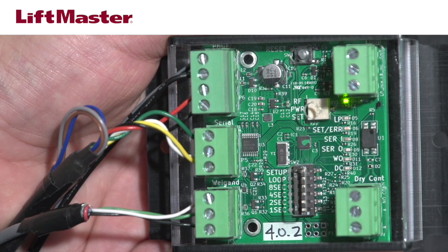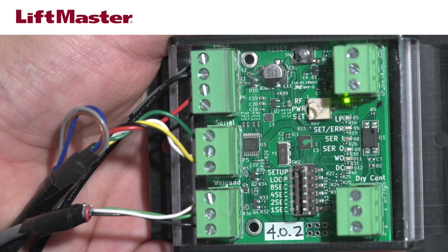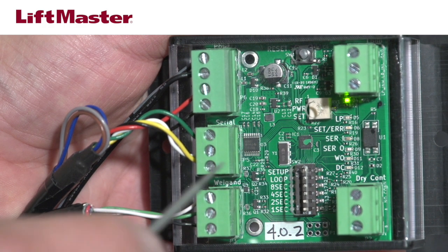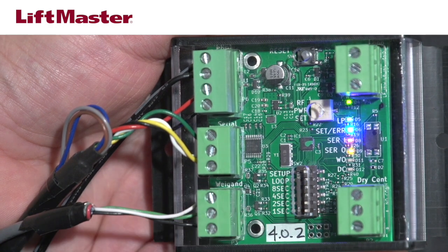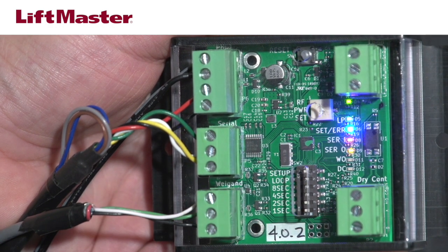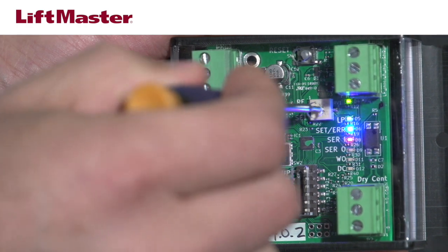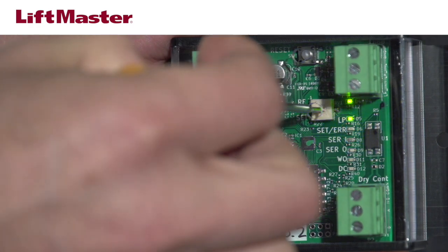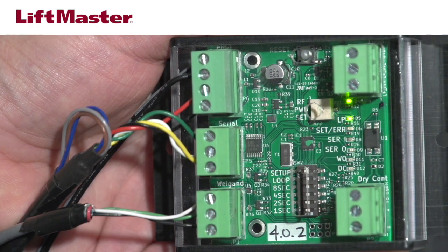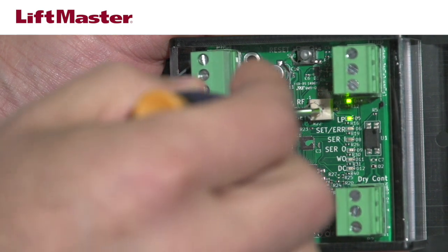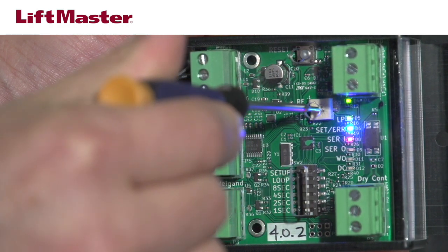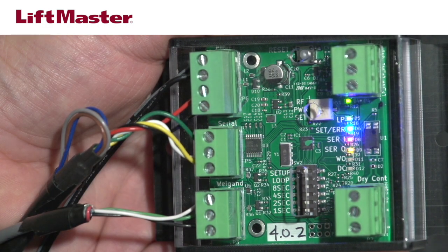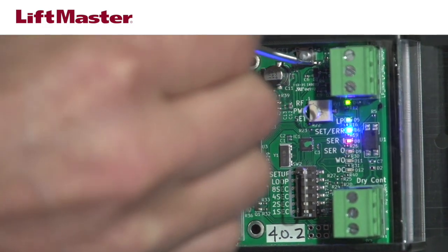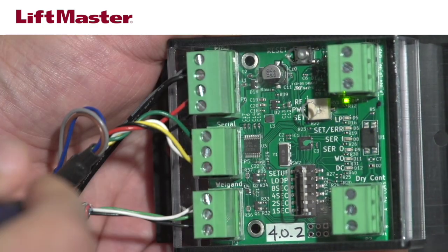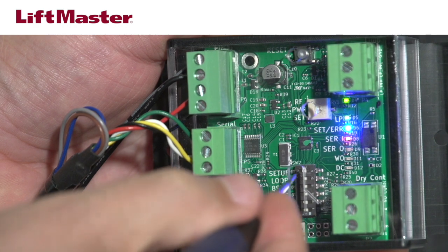The Wiegand interface module has an antenna range adjustment located on the circuit board. In certain cases, you may need to adjust it. Move dip switch number 6 to the on position to enter programming mode. Locate the adjustment pot and turn clockwise to increase range or counterclockwise to decrease range. The LED display will show the relative power setting. More LEDs means more power. Press the reset button to send the new range setting to the reader. Now move dip switch number 6 to the off position to go back to operating mode.